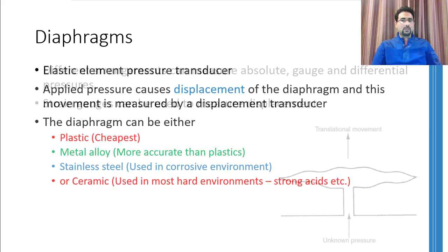In industry, diaphragms can be made of different materials ranging from plastics, which are the cheapest and most sensitive, to the ceramics, which are the least sensitive and most expensive ones. Normally, metal alloy diaphragms are used in industrial settings because of their superior accuracy. However, if the fluid of which the pressure is to be measured is corrosive in nature, then stainless steel diaphragms are preferred. Ceramic diaphragms are only preferred in case of harsh environments where stainless steel diaphragms cannot work.